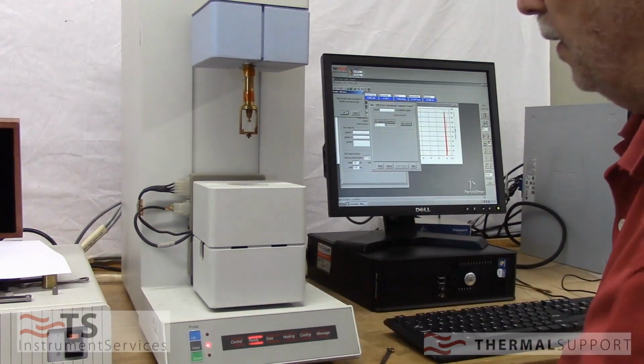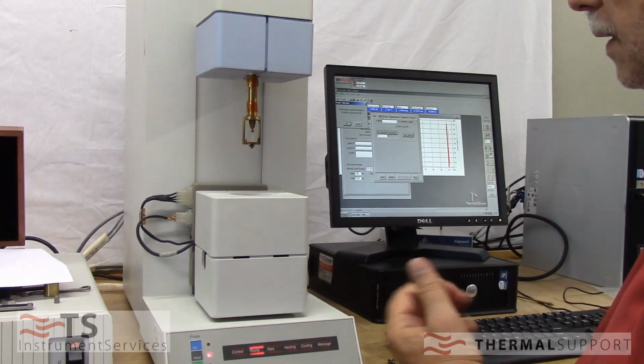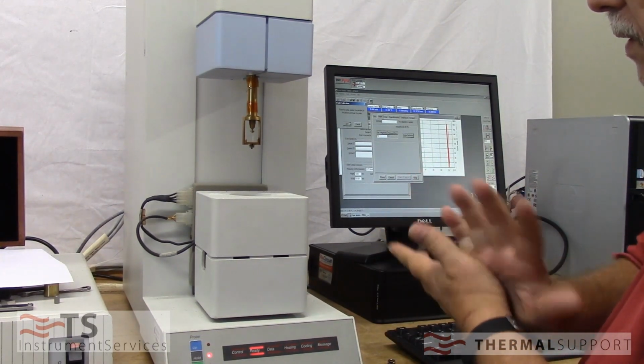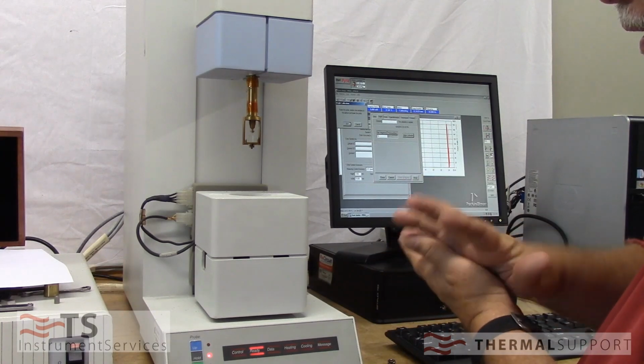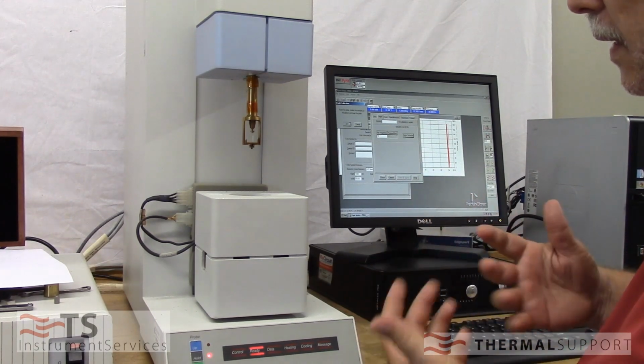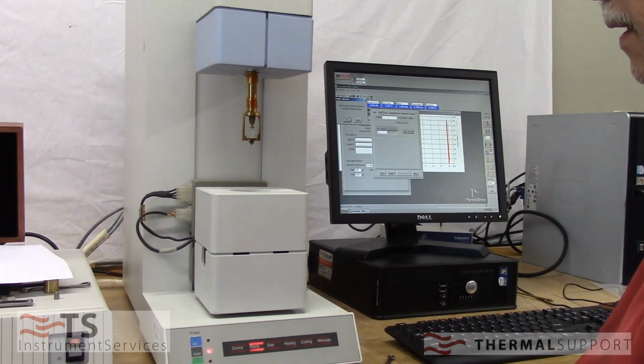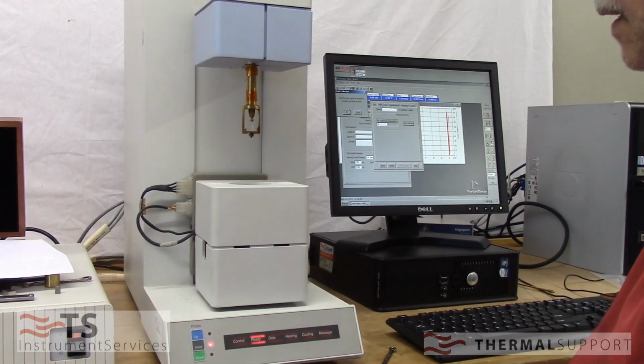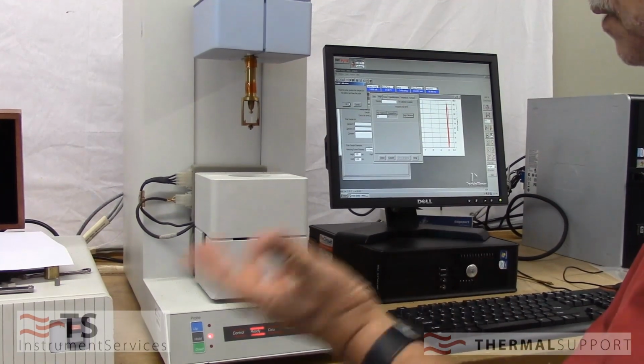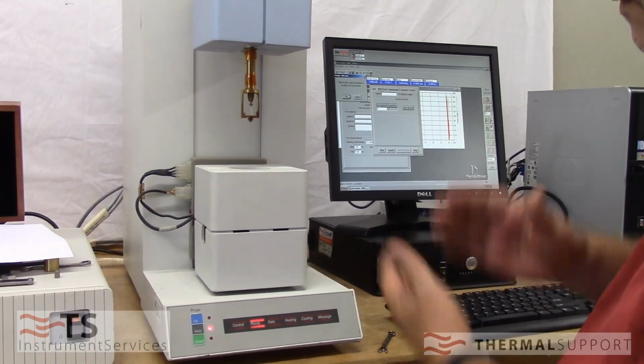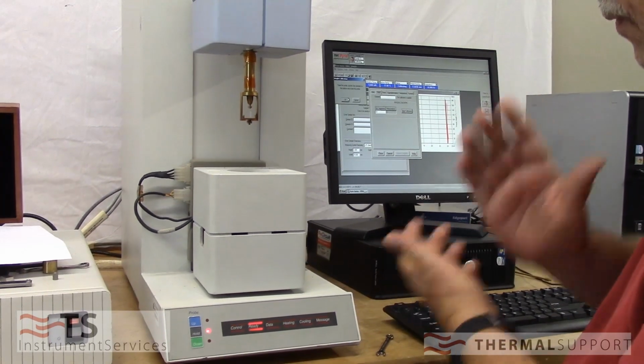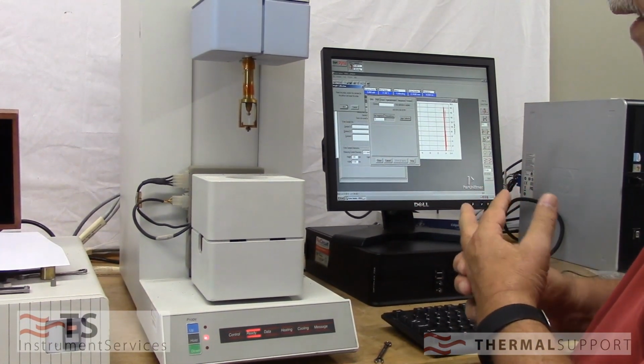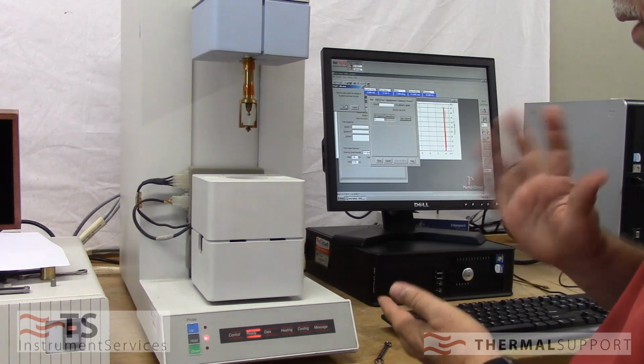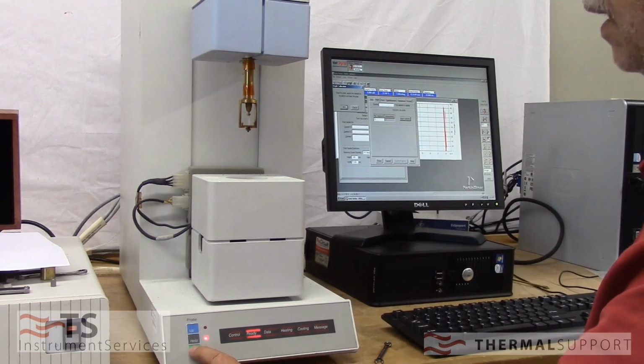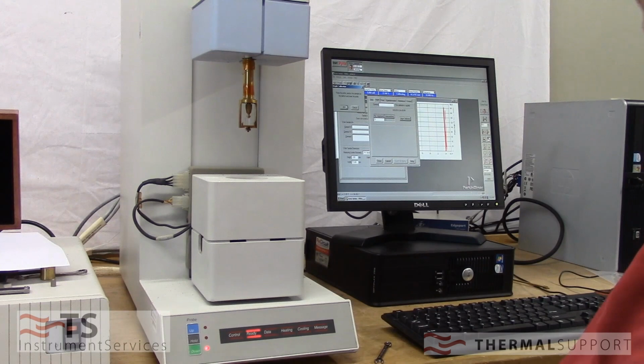Some of these 3-point bendings will have a little post in there, and if you get one of those that's not quite smooth, it can get a little rocky. So you can always put a parallel plate in there that is absolutely going to be smooth. This one here is smooth, so we're fine with it. But I have seen several of them that for one reason or another were not as stable as they should be. So if you see one's a little rocky, it's a good idea to change it. Probe's up, probe down, and we're going to say OK.